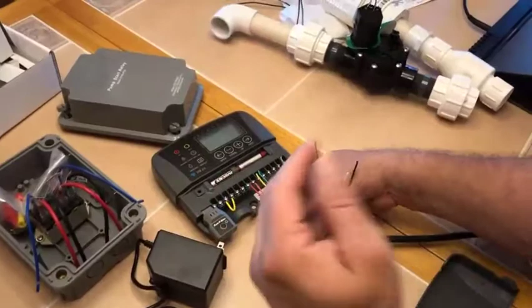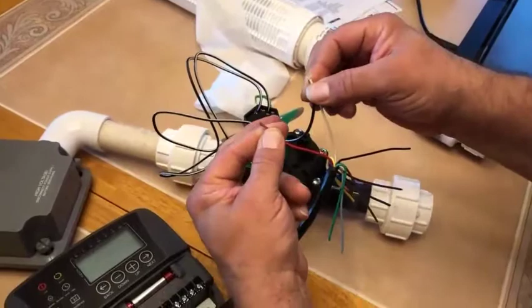Just a simple thing. Now when I get to my actual valves, for example over here, the other end of the wire needs to connect up to the solenoid wires here. Again, like the pump relay, it doesn't matter which one since it's low voltage. For this valve I'm going to connect my white wire as a common, and my red wire to the other lead. By putting the red into spot 1, that's now going to turn on zone 1, or turn it off when the timing is done.